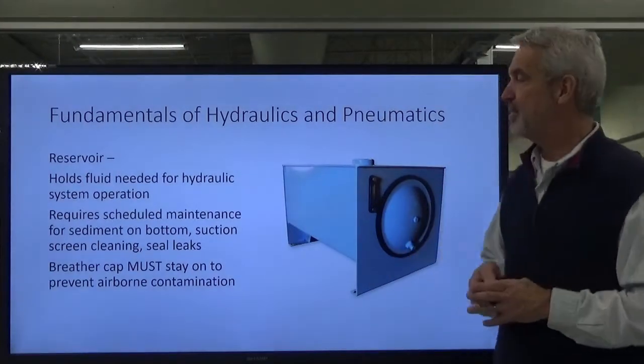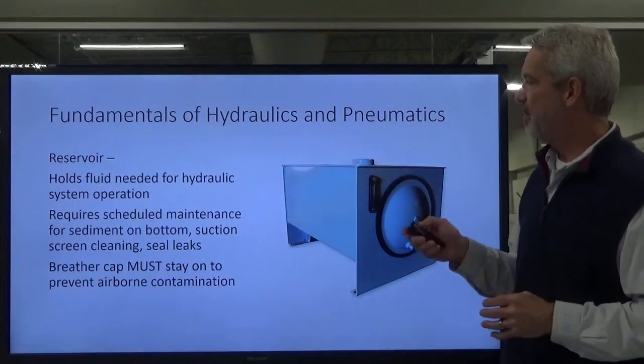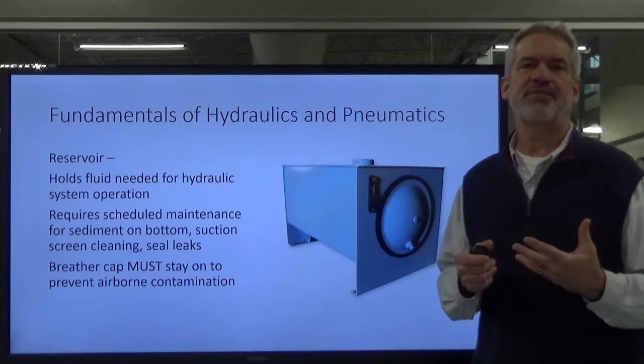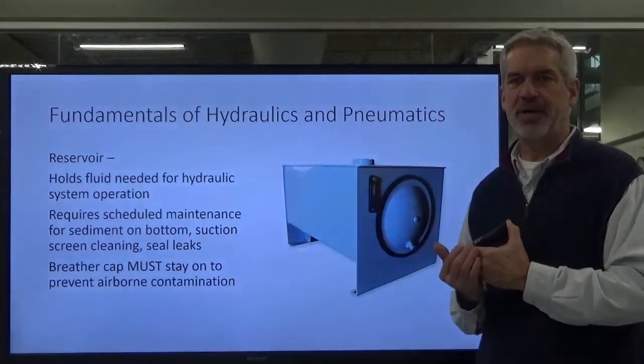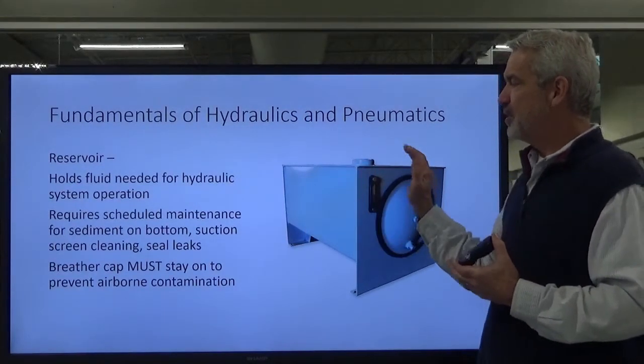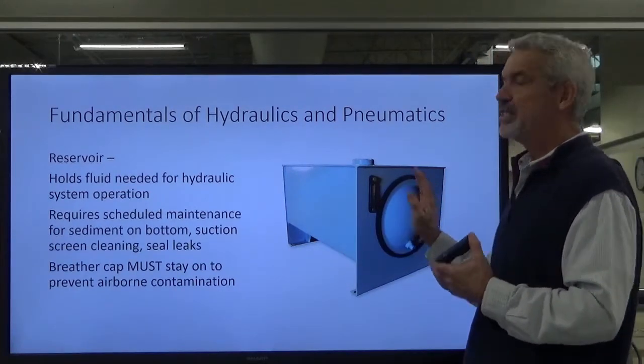Remove all sediment because you want your oil to be nice and clean so that the valves don't start sticking, so that the debris that's carried in the oil doesn't start cutting seals on the cylinders and start puking oil out on the floor. This breather cap, it's got to stay on all the time. I'm going to show you a better picture of it. A breather cap, particularly in an industrial environment, every time you have a cylinder or actuator that actuates, you're evacuating oil.